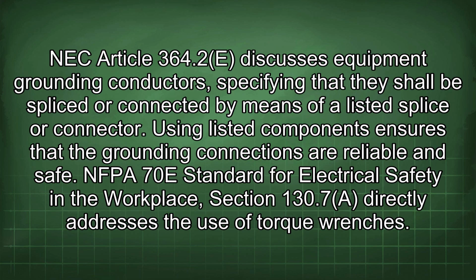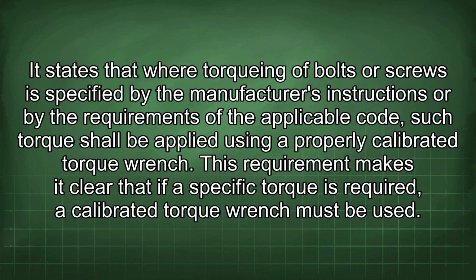NFPA 70E, Standard for Electrical Safety in the Workplace, Section 130.7 directly addresses the use of torque wrenches. It states that where torquing of bolts or screws is specified by the manufacturer's instructions or by the requirements of the applicable code, such torque shall be applied using a properly calibrated torque wrench. This requirement makes it clear that if a specific torque is required, a calibrated torque wrench must be used.